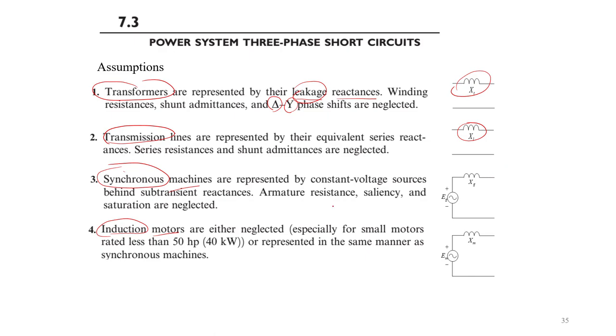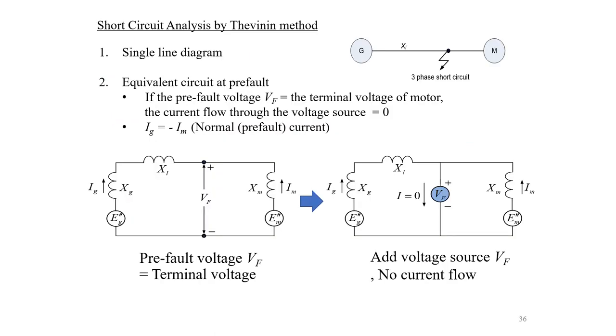Assumption number three: synchronous machines and induction motors are represented in the same fashion as a constant voltage source behind subtransient reactances. This same model applies to both the synchronous machine and the induction motor — consistent with the assumptions used in the past two examples.